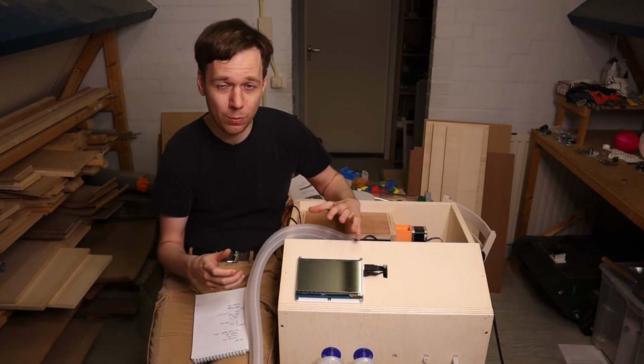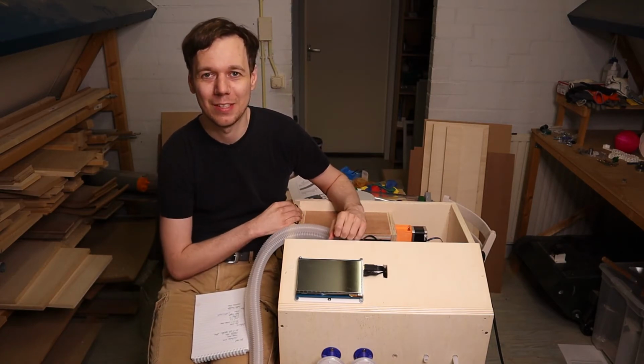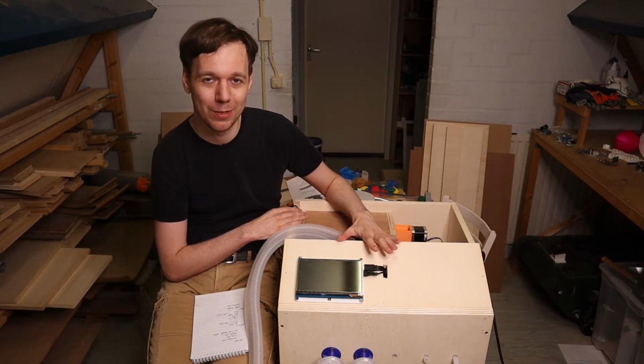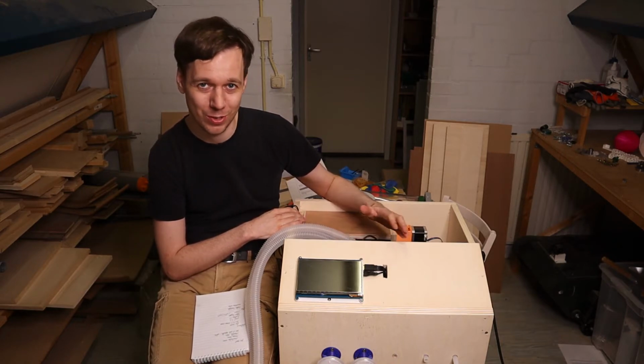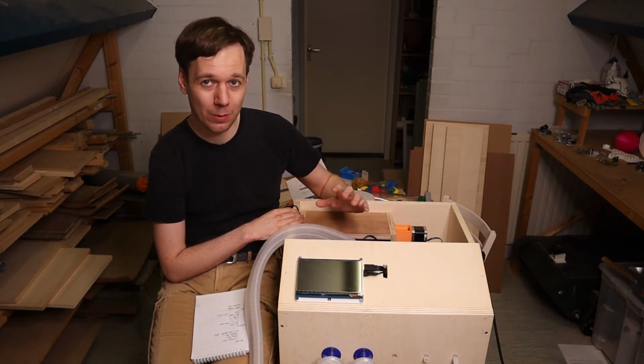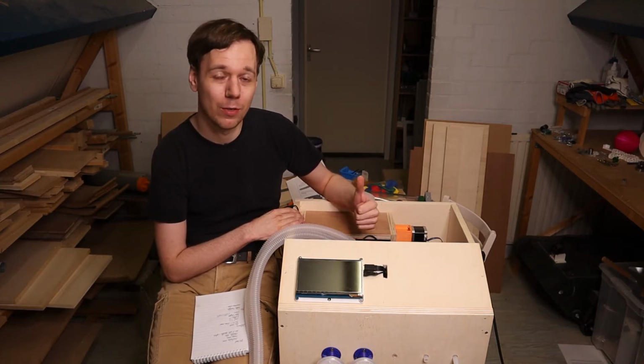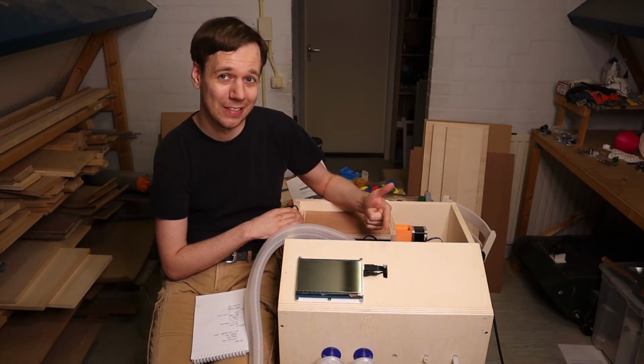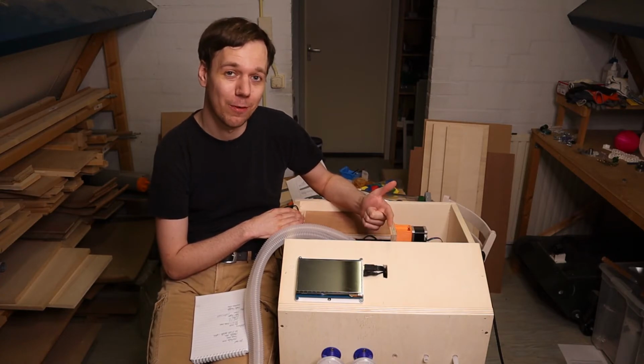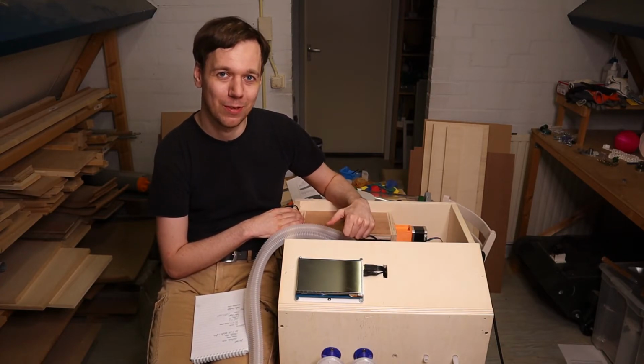Once that's all done, of course, there's also the kind of obvious thing that you have to test the device, run it with increased oxygen concentrations, and check that you, first of all, can deliver variable oxygen concentrations, and second, test that the thing doesn't set itself on fire, because that's kind of a big risk with increased oxygen.